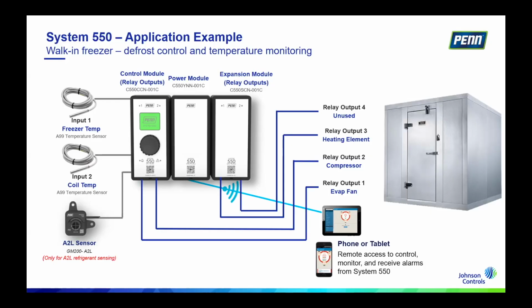What do we mean by that? Well, we mean that if the unit now goes into mitigation, typically what will happen is the compressor will shut down, the evaporator fans will be on, and will typically go to full speed if they're variable speed or multi-speed. You'll shut off the heating element if it's on, and you will then lock out basically the system for 5 minutes, which is a requirement by UL 60335. Once the LFL, or the lower flammability limit, is reached for that refrigerant leak, you'll maintain that 5-minute lockout, and then the control will actually allow you to resume operation after that 5 minutes.